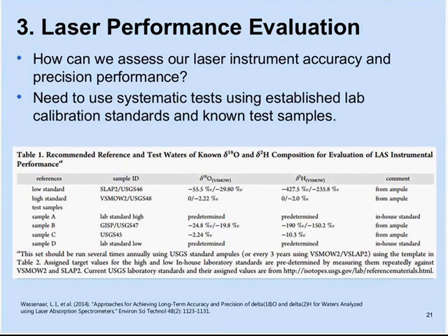The second thing you'll need is samples, which are denoted as A, B, C, and D here, where you also know the isotopic composition very well. And there are some suggestions given here, for example GISP or USGS-47 or 45, which lie in between VSMOW and SLAP. We left a couple of blank spaces there called lab standard high and low. These would possibly be your own laboratory standards, where you've already got some numbers or you've had numbers provided to you, so you can see how well you can meet the accuracy and precision criteria.